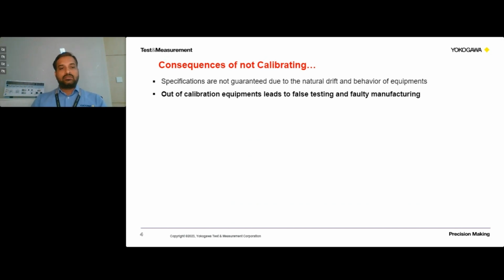And out of calibration equipment leads to false testing and faulty manufacturing. Let us say, for example, an instrument in the production facility is not calibrated on time. If we test our products using that out of date calibrated or non-calibrated instrument and proceed to manufacturing, we may end up having faulty products at the end of the day.